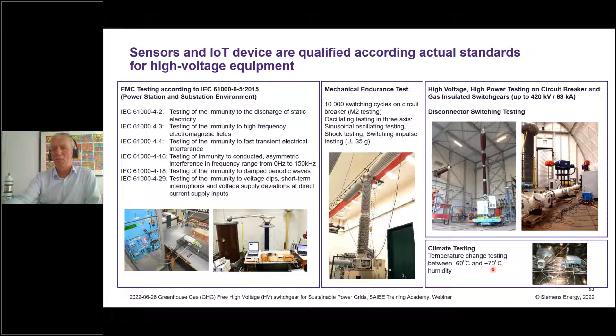The problem with sensors is they always have lower reliability than the high voltage equipment itself, which is often the case in automotive and elsewhere. So we tested all the sensors and the whole systems thoroughly with EMC testing, mechanical endurance tests, and high voltage, high power testing, which you see in our testing departments. The whole system, SenseFormer, SenseGear, was tested at lowest and highest temperatures to achieve the highest possible reliability of the whole sensor and connectivity system.